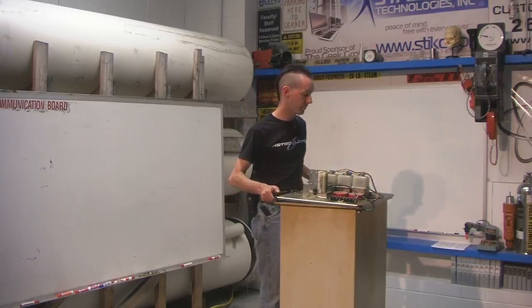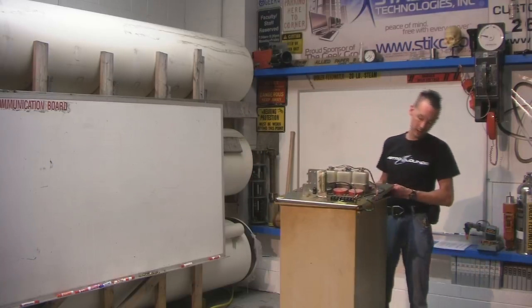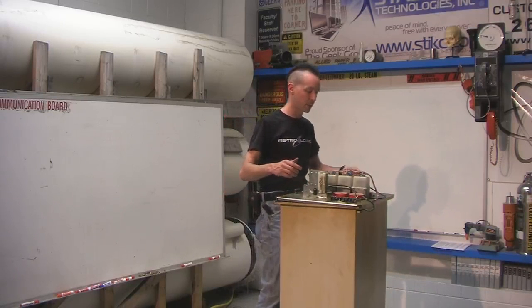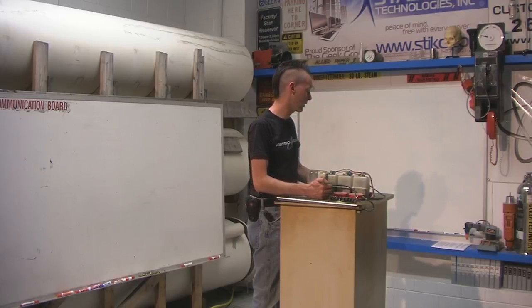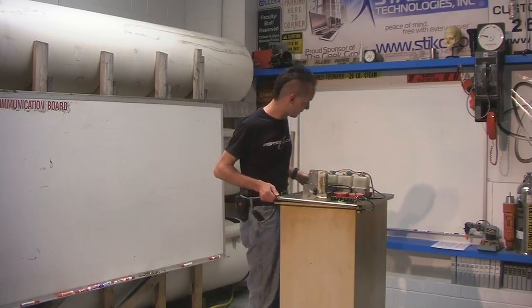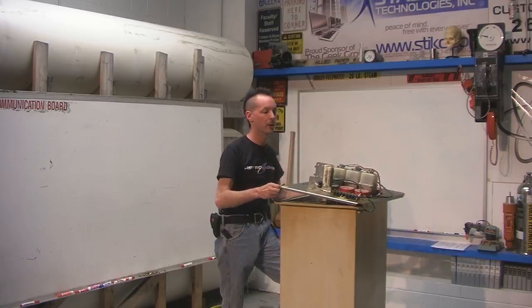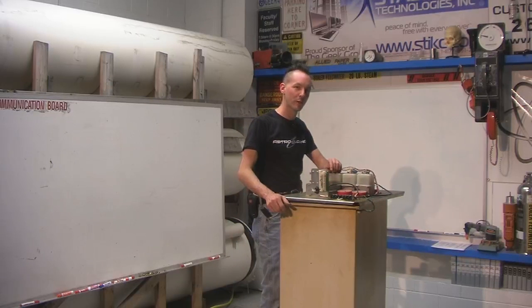Oh, this is going to suck. That old familiar smell — mineral oil. If you're working on a Philips Medical Systems transformer — which this is — the same rules apply. You don't have to worry about PCBs if it's a medical class transformer, because neither Philips Medical Systems nor General Electric has ever used polychlorinated biphenyls in their oils in medical grade transformers. This is going to be particularly difficult to lift up. There are a lot of connections under here, and I need to break these. Get a forklift over here. We'll be right back after this brief moment of Mikey getting the forklift.